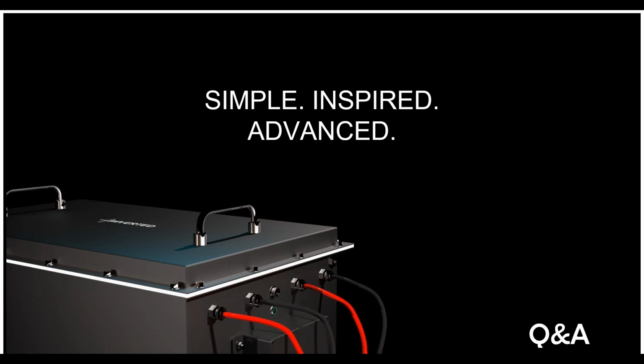To Priyank's question, what is the depth of discharge for a lithium-ion battery? It is about 80 to 85%. The higher the depth of discharge, the lower the number of cycles. While you can discharge these batteries to a depth of discharge of 95%, that would have an implication on life cycle. So it is recommended these batteries should be operated at a DOD of 80%.